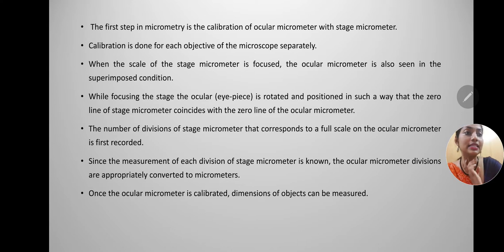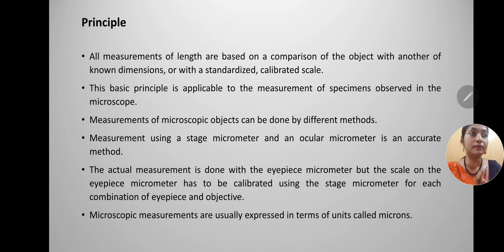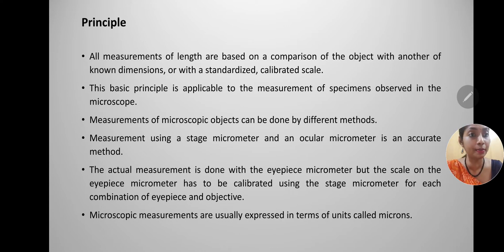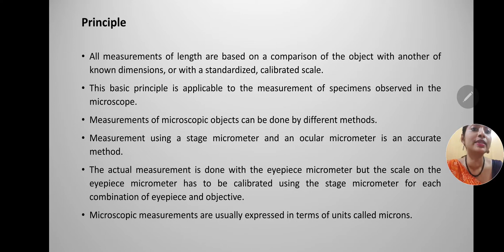Now let us understand the principle with the help of an image. All measurements of length are based on a comparison of the object with another of known dimension or with a standardized calibrated scale. This basic principle applies to measuring specimens in the microscope. Measurement using the stage micrometer and an ocular micrometer is an accurate method. The actual measurement is done with the eyepiece micrometer, but its scale must be calibrated using the stage micrometer for each combination of eyepiece and objective. Microscopic measurements are usually expressed in microns or micrometers.